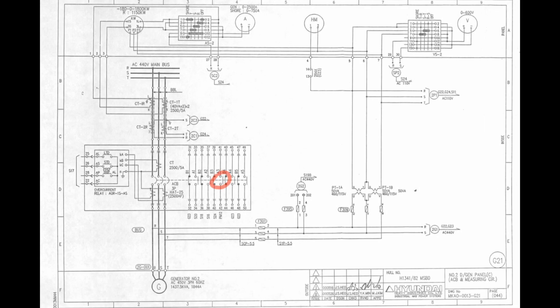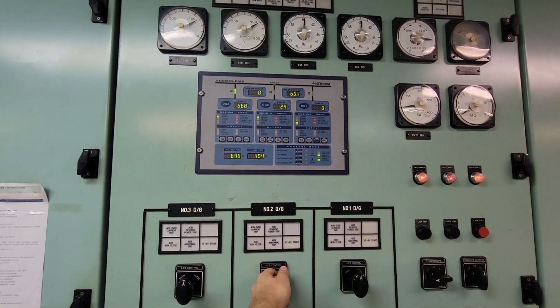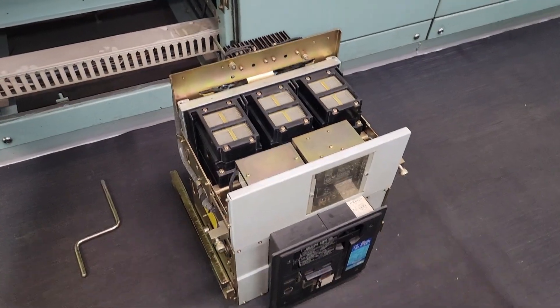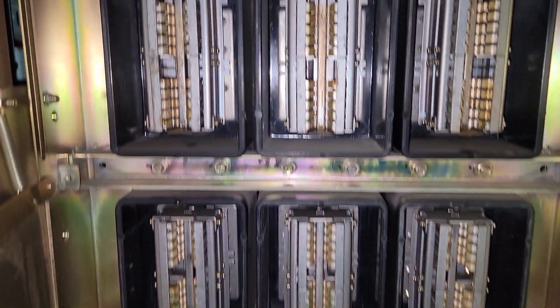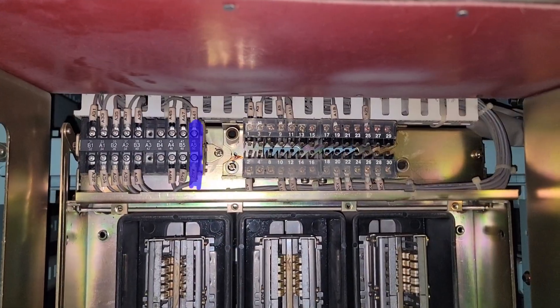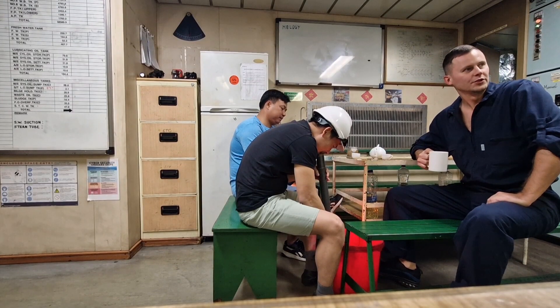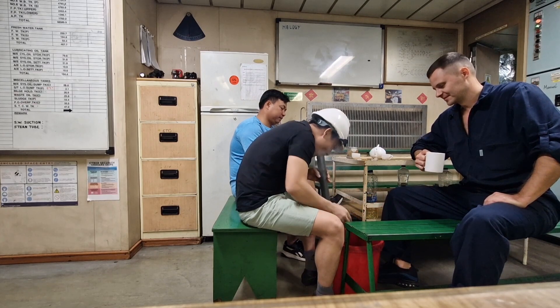Now, in order to fix the problem, we need to find and replace this contact. It is located behind the generator ACB. Switch to manual mode and remove the generator from the bus bars and stop the diesel. Remove the ACB and reconnect this normally open contact to the spare one. When doing this work, do not forget about safety rules and electrical lockout-tagout procedures. Thank you for watching.